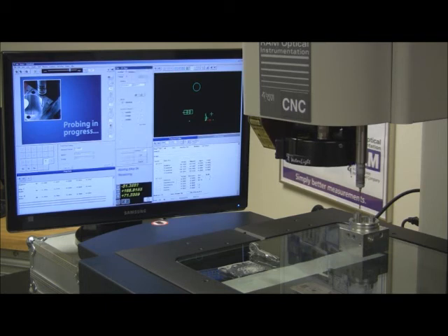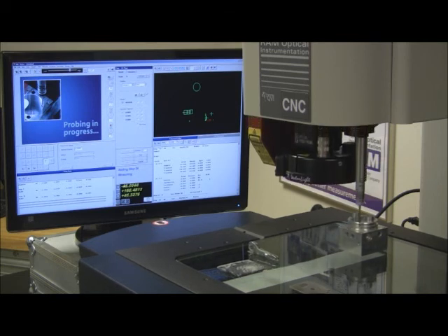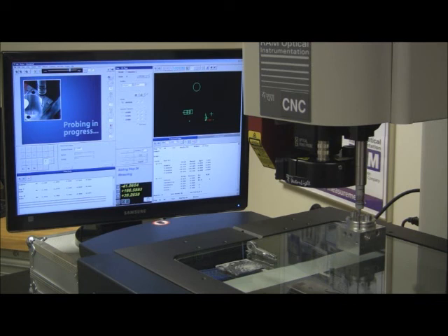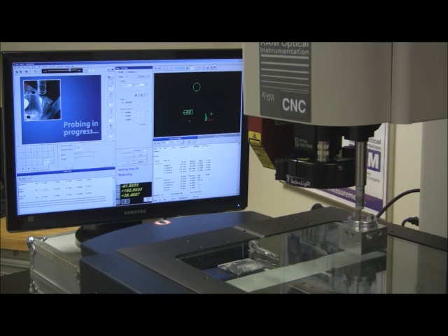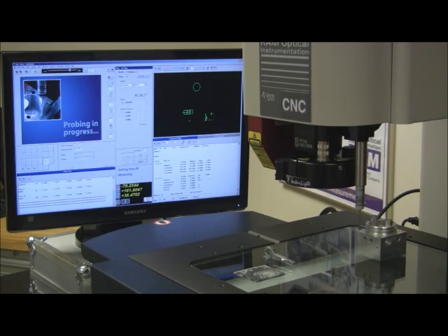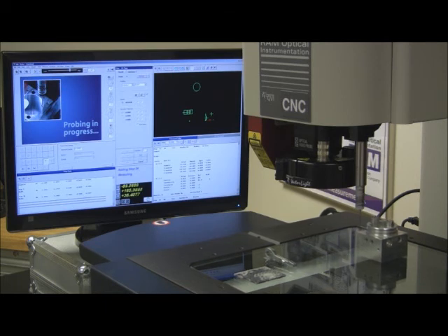I'm going to move down to the corner of the part, and again I'm moving the machine with the joystick. I'm down at the corner where I want to be. I hit the enter key to record my position. I touch the surface and the machine automatically backs off from where I was. I'm going to move out a little bit so I don't hit the diameter as I go across. Come back in, touch another point, the machine automatically backs off.